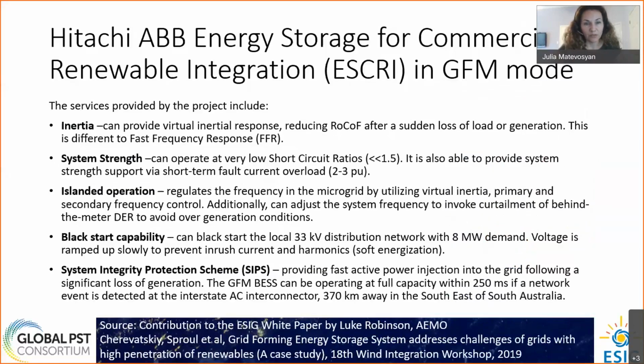So services provided by this project include inertia. It can provide virtual inertia response, reducing rate of change of frequency during sudden loss of generation or load. This is different to fast frequency response. Again, it doesn't need frequency measurement to respond and responds in the way a synchronous machine would do. There is instantaneous injection of active power in response to change in voltage angle. It can operate at very low short circuit ratios, and it's also able to provide support via short-term current overload to the system.